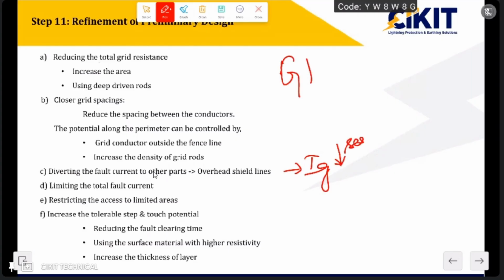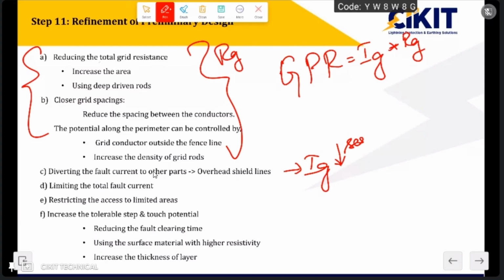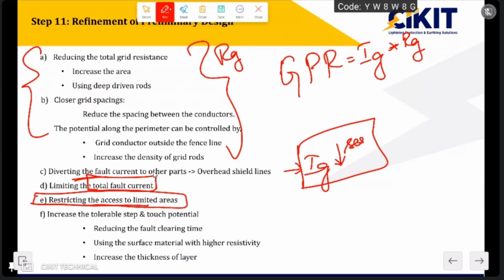As I mentioned, the value of GPR is nothing but the product of Ig and Rg. If I take the first two points, here we are reducing the value of Rg. But in this third point, I am reducing the value of Ig. And the fourth one is limiting the total current. We won't go for this method mostly, but that is also an available option. We can make some arrangements for reducing the fault current levels on particular sections. And the final one is restricting the access to limited areas. Here we are considering the safety of the person, and by providing fences and restricting access to people into the substation area, we can avoid damages. So restricting access will be one of the solutions for reducing the damages due to step and touch voltages.